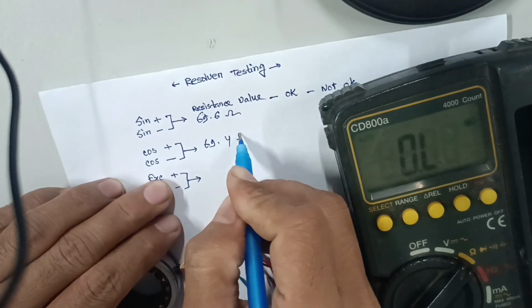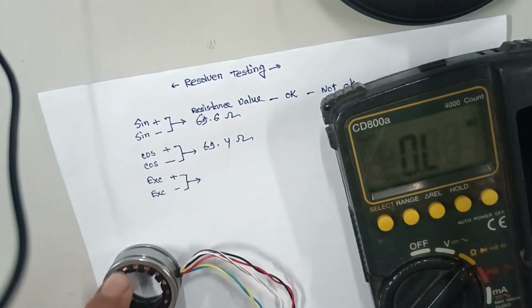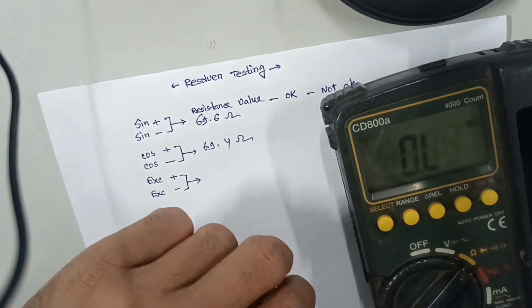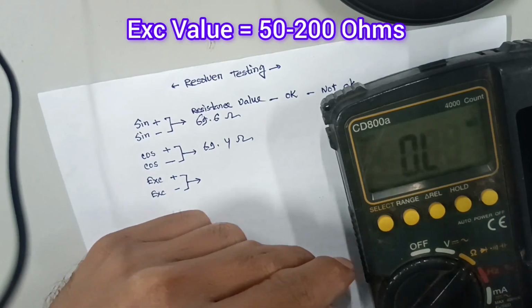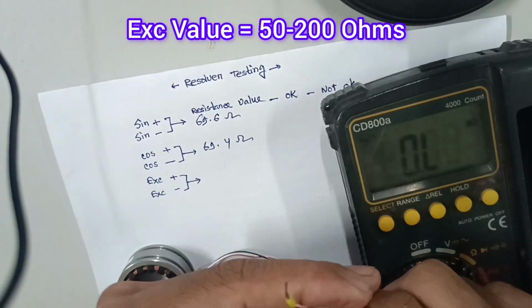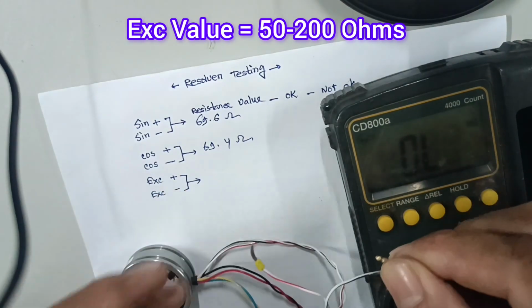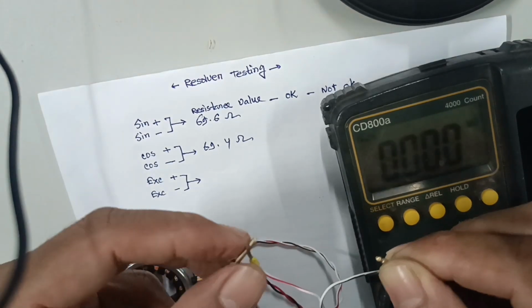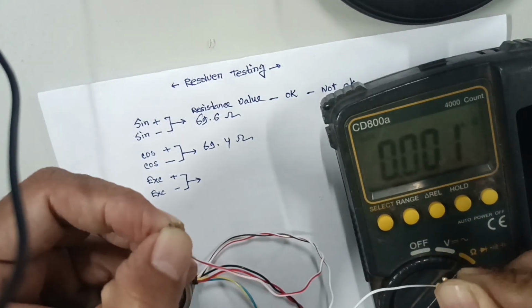69 point something, still okay. But before that, I test the excitation coil - if I get the excitation coil within the range of 50 to 200 ohms, as per the resolver OEM's written note, it will be okay.